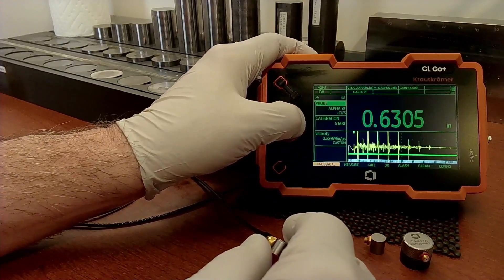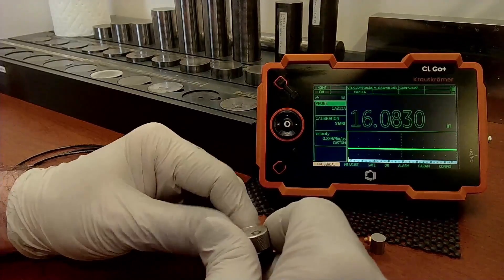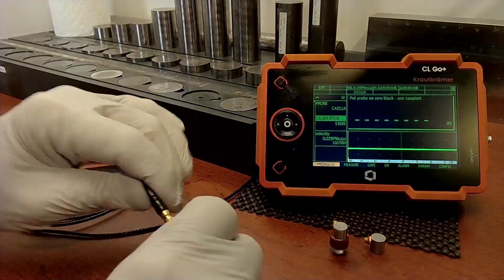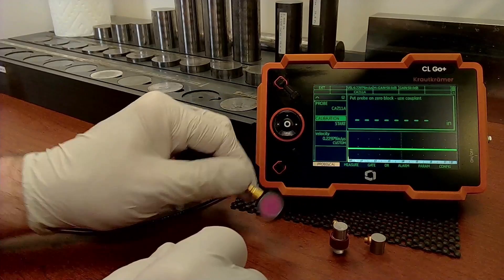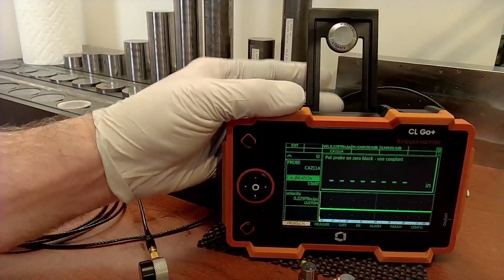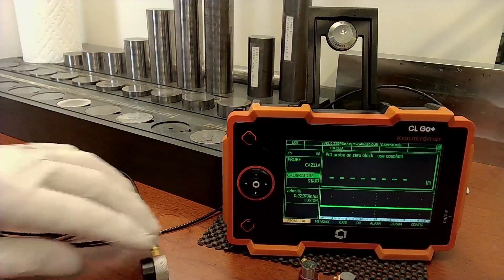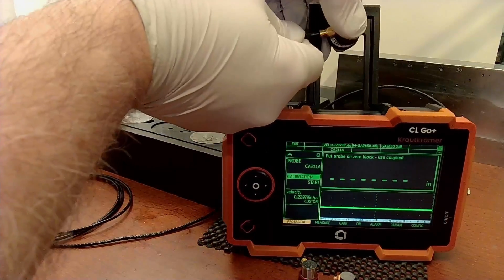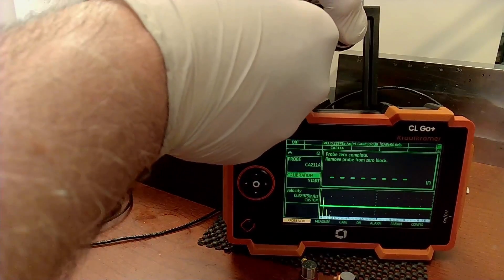Let's take a look at a different probe. We'll switch to the CA-211 probe. Now the CA-211 is typically used for a little bit thicker materials. So let's do a calibration. Now, there's two steps to calibrating a direct contact probe. The first step is used to establish probe delay. And to do that, we have a zero block that is built into the kickstand of the instrument. So put just a drop of couplant on there. And we couple our probe to the zero block. And the instrument acquires the data from the zero block.